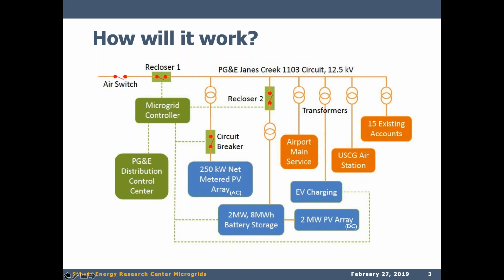Both of those resources will be in grid following mode. If there is a disturbance on the main grid, so power goes down, the controller will identify that, open recloser 1, and isolate the microgrid into island mode. At that point, the smaller array will go offline because it has anti-islanding features like any typical grid-connected array. The battery and the PV array connected to the battery will then be brought online to form the grid and serve the loads. After 5 minutes, the smaller array, which says 250, that's an AC rating, will come back online. That's the normal protocol, and then it will continue to run.